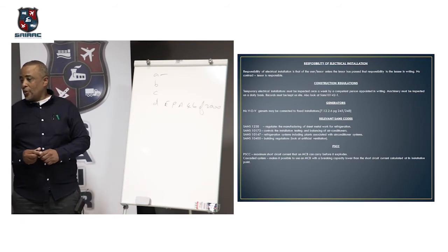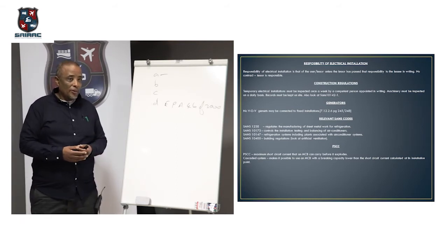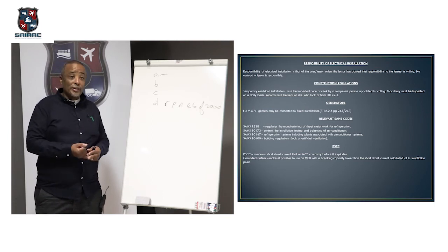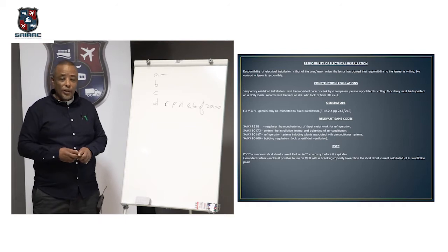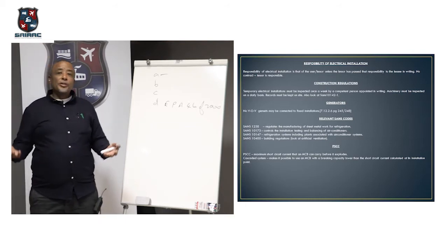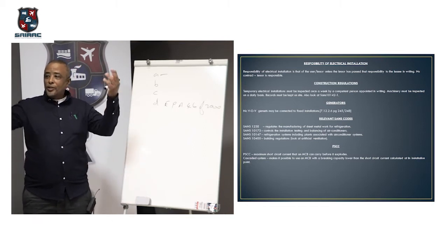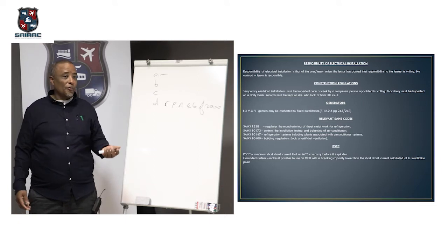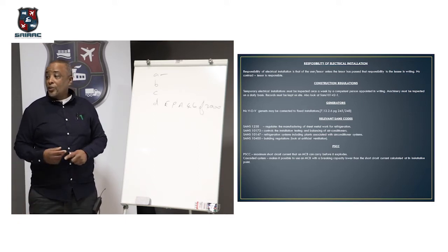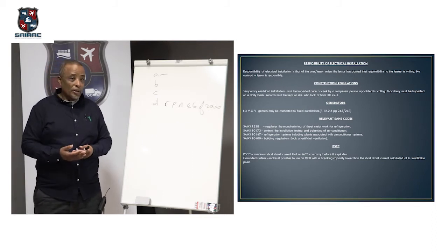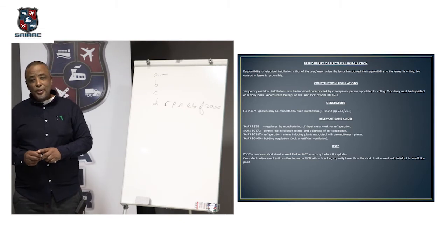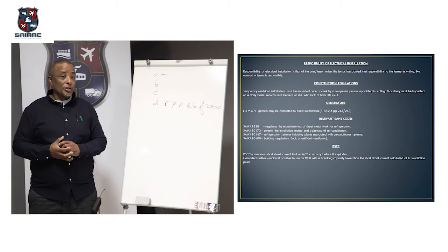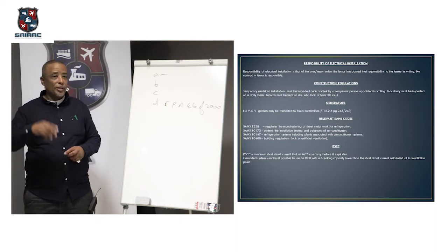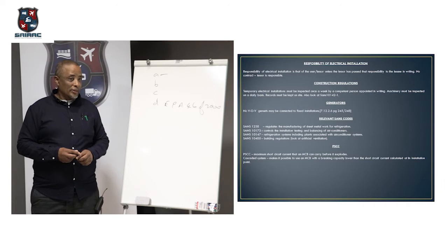Your material: nobody should sign off a job if you don't have the paperwork for whatever equipment it is in any area, especially in a hazardous area. It's very important that you know that you have the paperwork. For instance, if a guy gives you a light fitting and wants you to stick it up, or you go to Voltex or wherever you buy a light fitting and you want to stick it up, flame-proof and weather-proof look exactly the same. You wouldn't be able to tell the difference. The only difference is the paperwork, it'll be classified. Very few companies do it under very stringent conditions, but they do classify it and say it's EXT or it's EXP. If you buy IP66 or 65, you just put there IP65. IP65 is water and splash and dust and that type of thing. It's not hazardous.